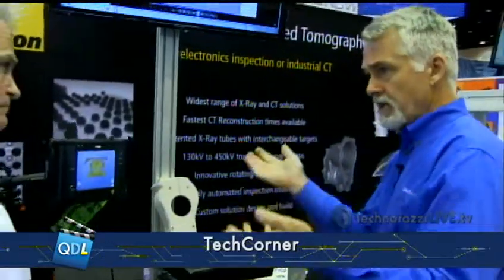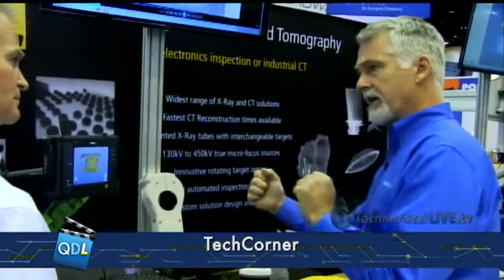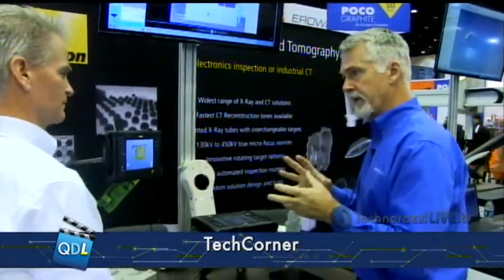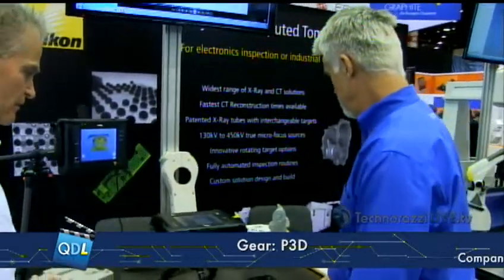So point cloud data, how is it output? What formats can you output it? You can do STL, PLY, and ASCII formats. Okay. Now, I think we were talking, obviously in that first shot you did one shot over the top, so there's some shadows. So if you were trying to get all angles, you could just keep taking multiple shots and it would combine them all together? That's correct, and that's where I would use the targets here.